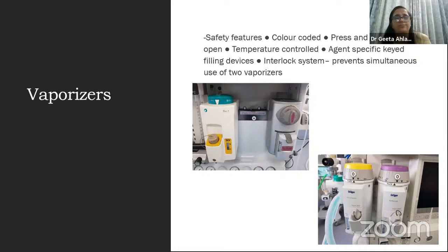Like in this figure, I'm showing you two kinds of vaporizers. They are not interchangeable. You cannot put a Dräger vaporizer on this machine. Then you should also see that the Selectatec mechanism is maintained. These vaporizers are color-coded and touch-coded. They are press and rotate, so if anyone accidentally tries to rotate, you cannot rotate. If one vaporizer is open, the other cannot open. Then they are temperature controlled and agent specific, and they have an interlock system so that two gases cannot be delivered even if someone makes a mistake. So these vaporizers have to be checked, and for the older ones, you must remember that the gas in them should not be very old.